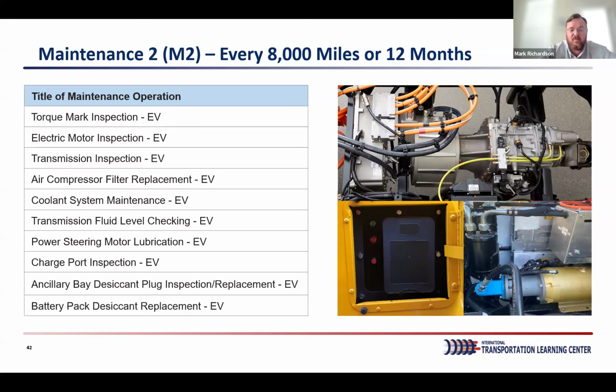When talking with customers about EV-specific preventative maintenance, we call out that on an annual basis, for this bus specifically, there's a desiccant filter in the battery packs that needs to be changed out. It's a simple task, but it requires decommissioning of the high voltage system.